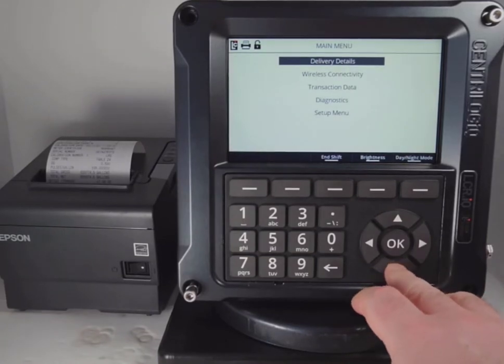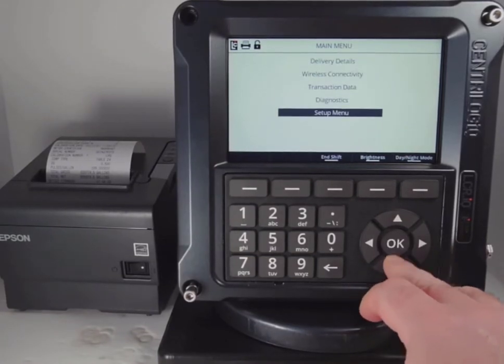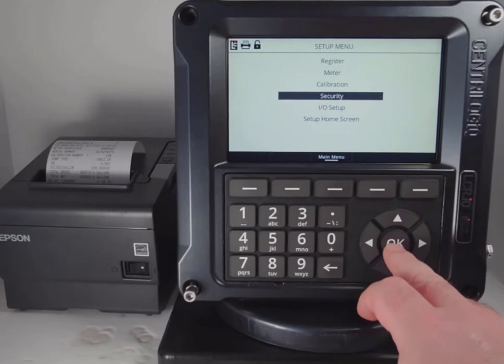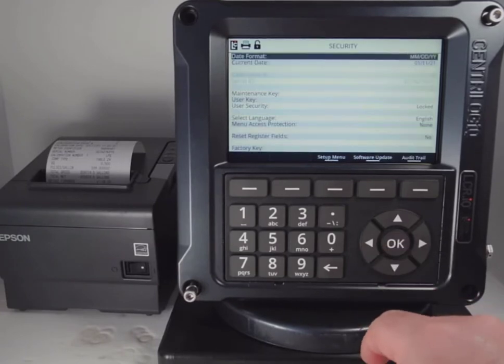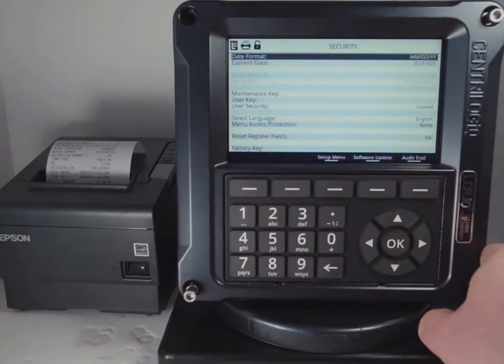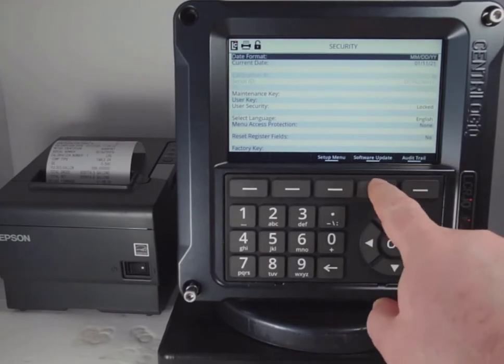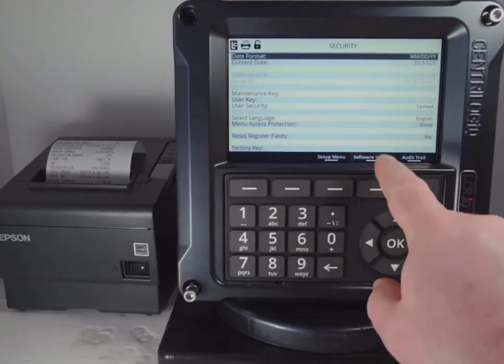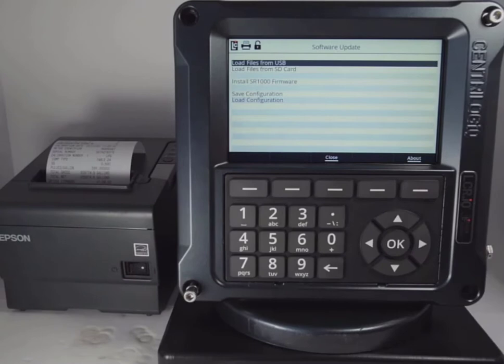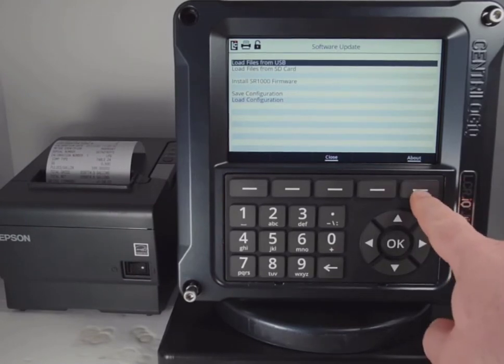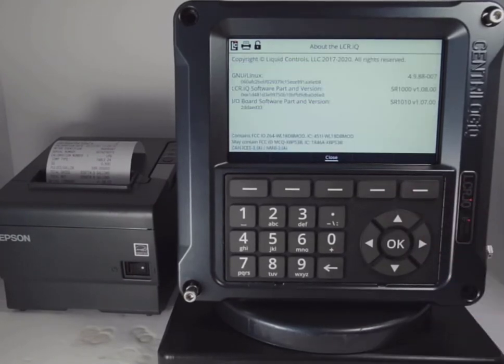Next, we'll use the keypad to navigate to the Setup menu, then to Security mode, and press OK. Once you're in Security mode and the unit is in the calibration position, you'll see a Software Upgrade button. If you press it, you'll see in the bottom right-hand corner an About button. When you press the About button, you'll see all the same information you would see in the diagnostics screen.